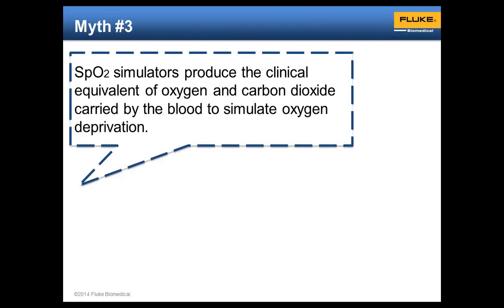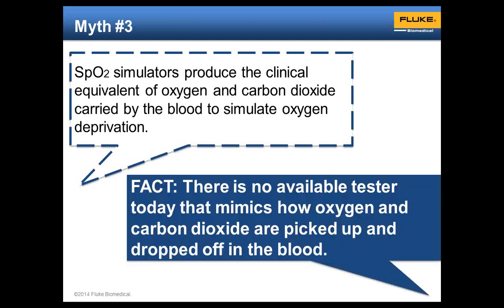So our next myth. SpO2 simulators produce the clinical equivalent of oxygen and carbon dioxide carried by the blood to simulate oxygen deprivation. There's no available tester today that mimics how the oxygen and carbon dioxide are picked up and dropped off in the blood. That would require fluid that can pick up oxygen moving through a pipe, basically. And so what happens is our testers mimic the R-curve through the light emission and not necessarily how the oxygen moves through the body.